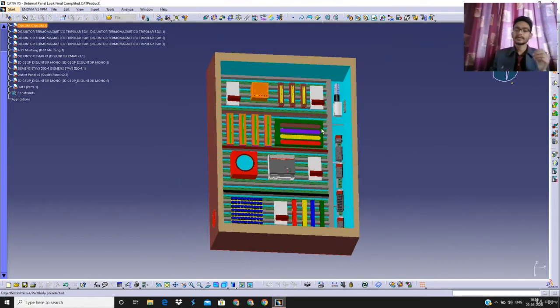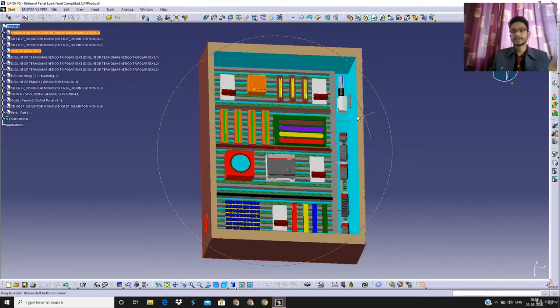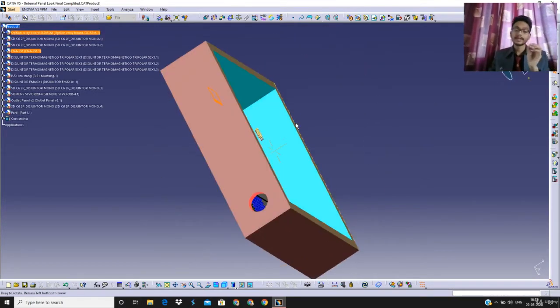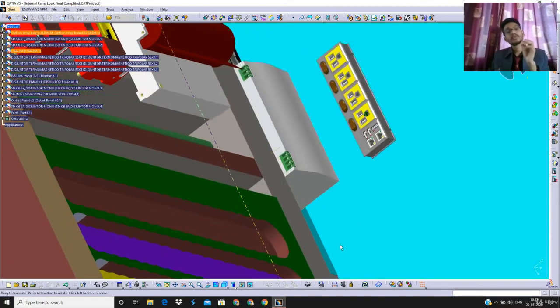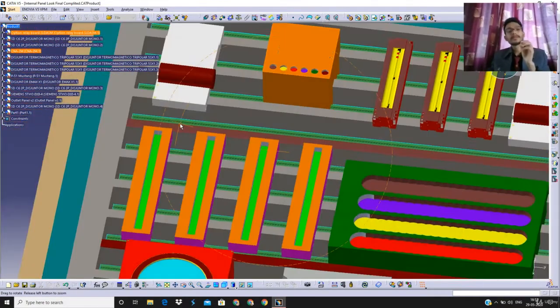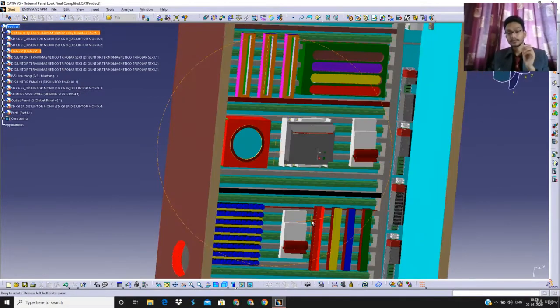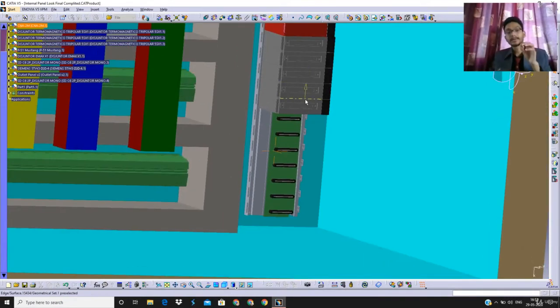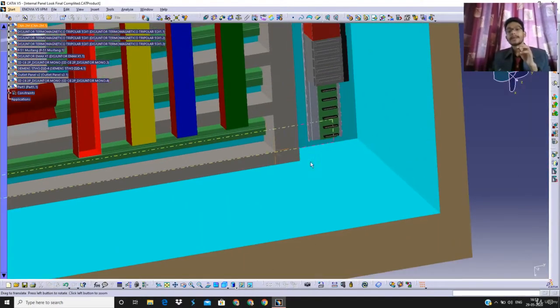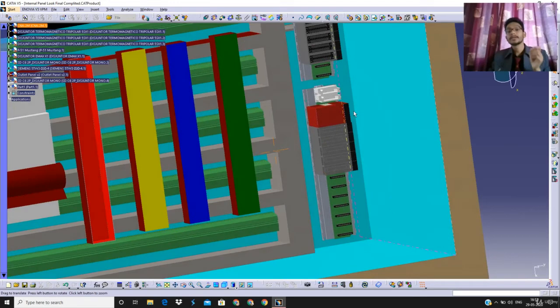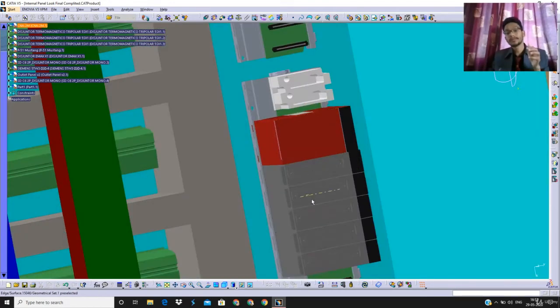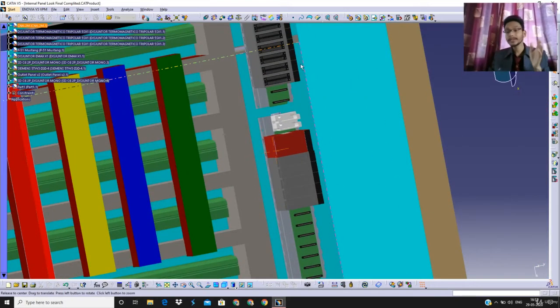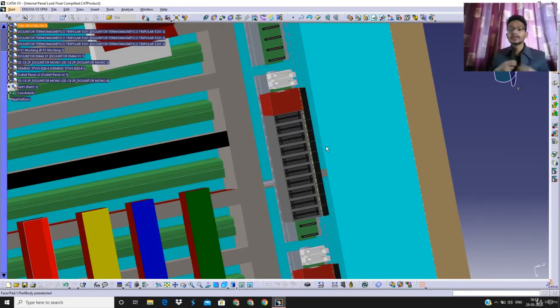And near to that you can see every location consists of an MCB. This means every system is subdivided along with its own protection system. And then we have a relay terminal box, which is the most important component of this control panel in terms of control connectivity with output applications. So this helps to control the digital outputs. That is, the output coming from the PLC can be used to turn on and off high power, high voltage applications, valves and different types of mechanical actuators, from the PLC along with this type of relay control box only.